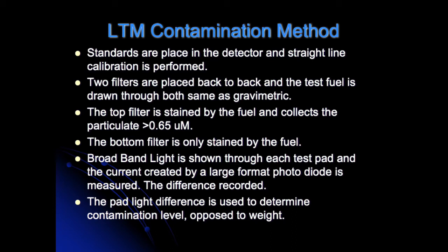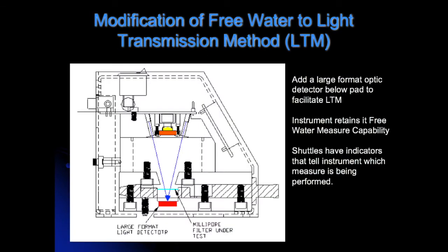The pad light difference is used to determine contamination level, as opposed to weight. Already employed in the field is the JFWA-1 Hydrolite, which is used for determining free water in aviation kerosene. We plan to modify the free water device to incorporate the light transmission method. To do this, all we have to do is add a large format optic detector below pad to facilitate the light transmission method. The instrument retains its free water measurement capability. Shuttles have indicators that tell the instrument which method is being performed using magnetics. Due to the design of the JFWA-1 Hydrolite, it is a very easy modification to add the LTM capability within the existing frame of the unit.